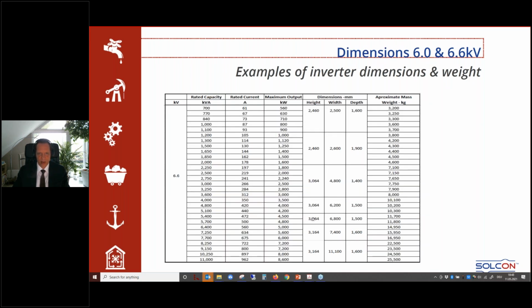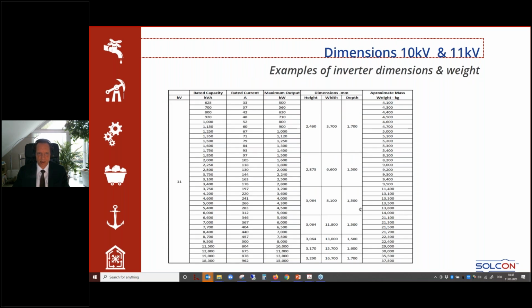6.6 kV, which is forming, let's say, the largest part of our inverter portions here, going from height 2.46 meter up to 3.1 in the very big portion, 1.6 meter depth here, and this remains more or less constant. 11 kV is another voltage which we see very often in the world. And the smallest one, 2.5 meter height, 3.7 meter width, depth 1.7. Depth remains more or less constant and goes up to a height of 3.3 and 16 meter width. That is really the monster here, 18.3 MVA. Approximate output is 15.3 megawatt. It can be higher, because very often it is synchronous motors and you start synchronous motors with the inverter starter with unity power factor. So that gives you, if a synchronous motor, even a higher megawatt or horsepower rating here.